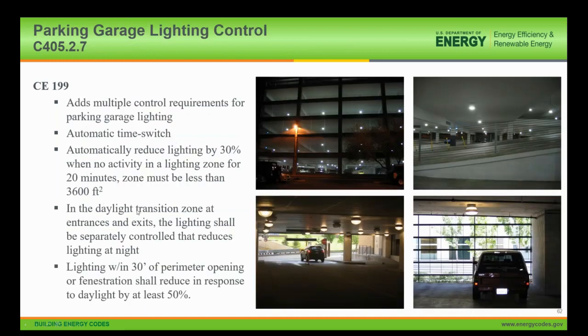Another change is requirements related to parking garage lighting controls. These four pictures really show why it makes a lot of sense. First, you need to have an automatic time switch. The picture in the upper left was actually taken at 1 a.m. in an exterior parking garage, and you can see all the lights are on. So there are some requirements, and that is what the IECC says about time switches. The picture on the right also shows why you might want to look at occupancy sensors.